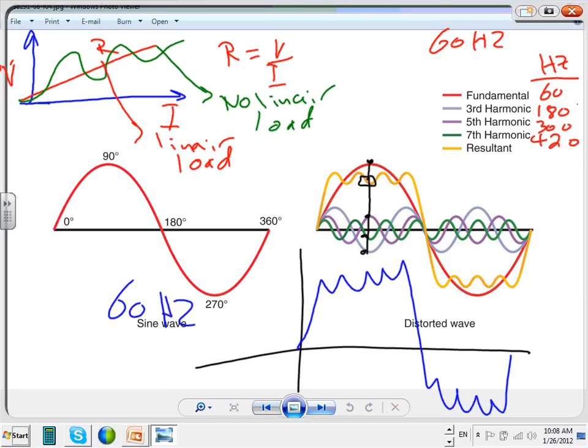I want you to highlight the third harmonic especially, guys. This third harmonic, without getting into proving it, when you have third harmonic, it adds up in the neutral of a 3-phase system. So if you have 10 amps, 10 amps, 10 amps, third harmonic, when you add them up in a 3-phase system, they don't cancel each other. They add up to 30. That's anti everything that we know about the 3-phase system. A 3-phase system is supposed to be balanced. If you have 10, 10, 10, what do you think the neutral is going to have? 0. That's why we love the 3-phase system.